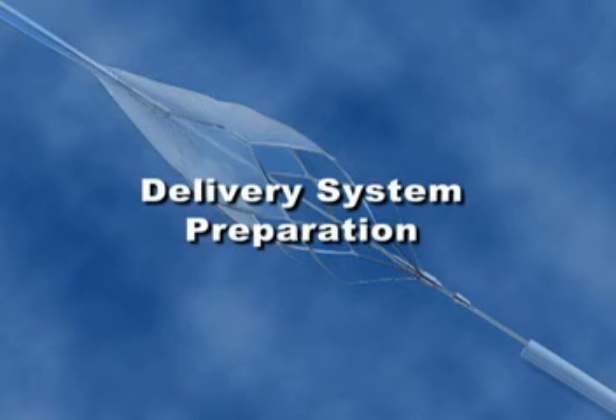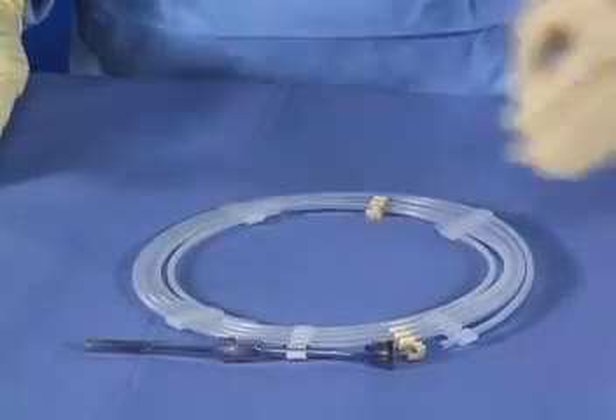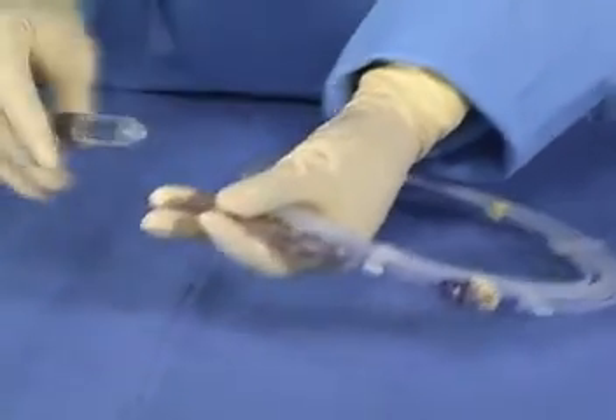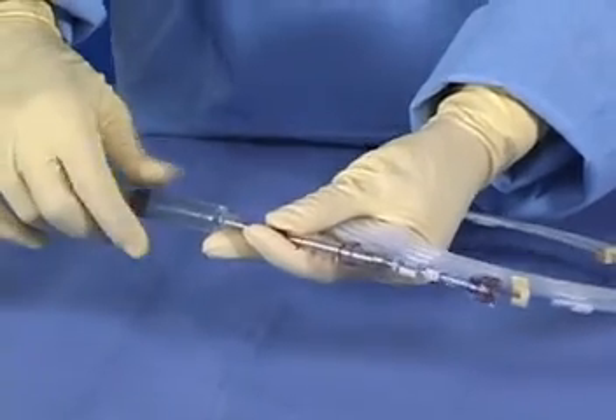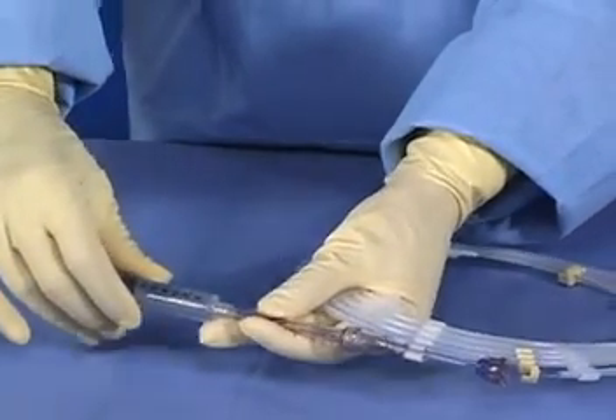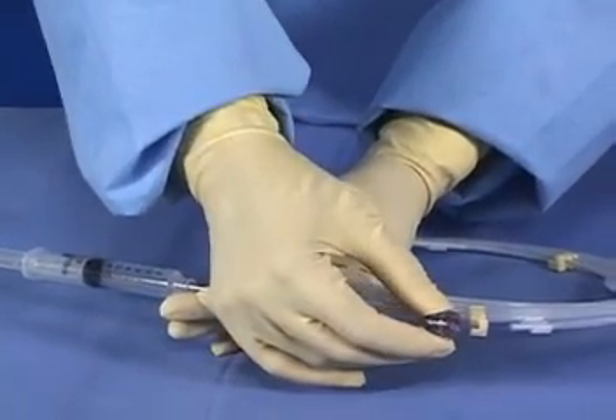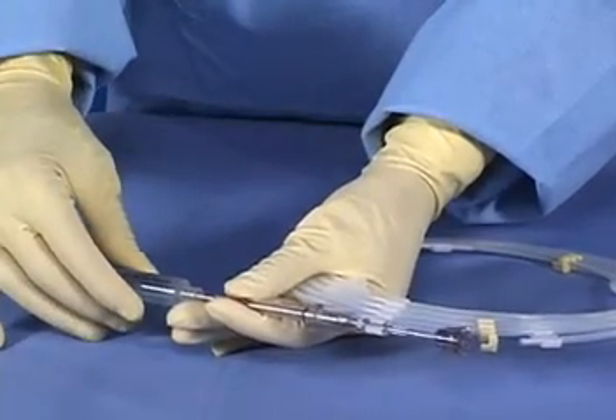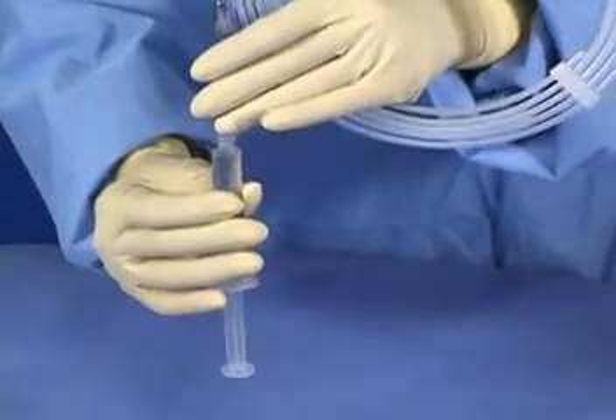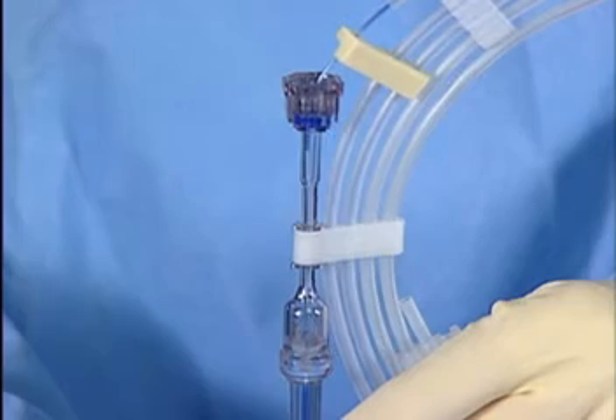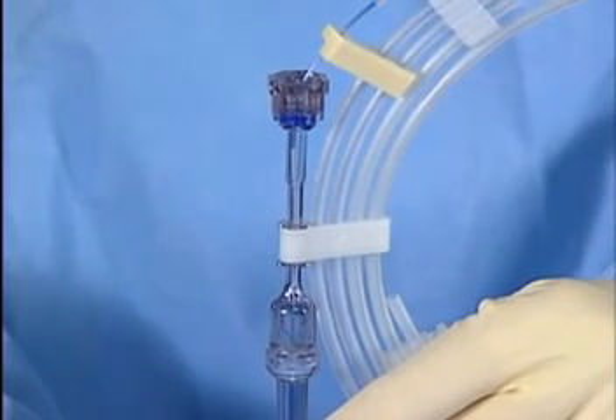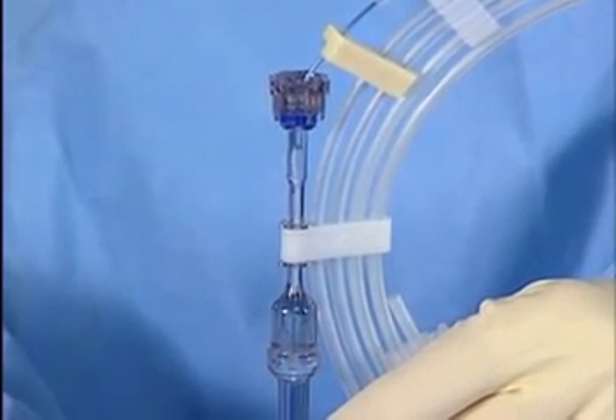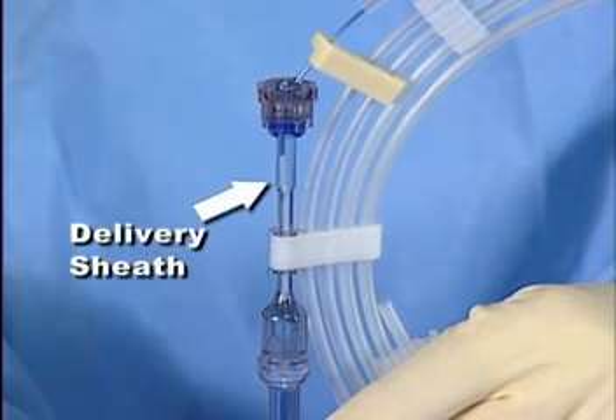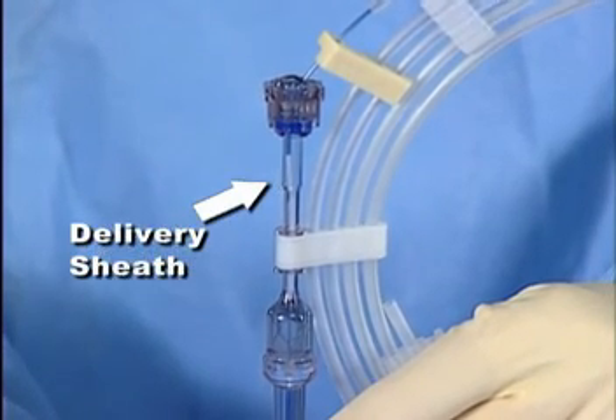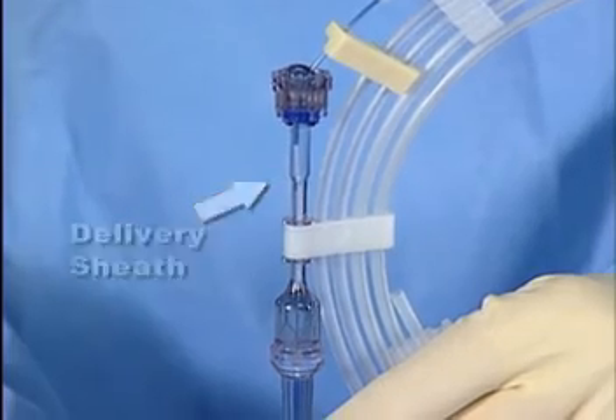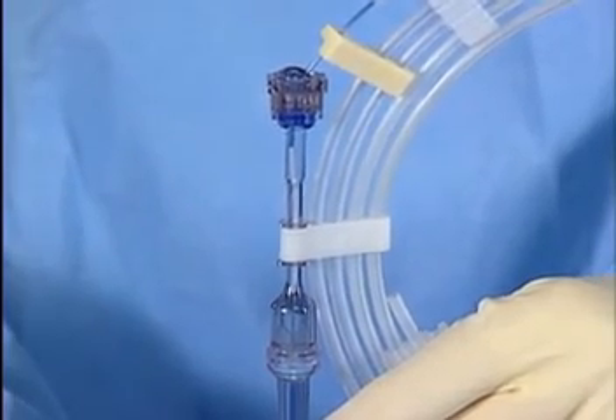Delivery system preparation. Attach a 10 cc syringe with heparinized normal saline to the flush tool. Confirm that the RHV on the flush tool is loosened. Hold the dispenser hoop in an upright position, then flush gently to remove air from the filter. Confirm that no part of the light blue section of the delivery sheath is within the valve of the RHV. Then tighten the RHV.